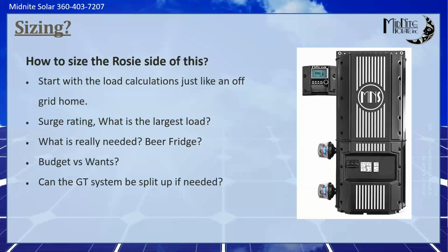But if the customer has, say, multiple strings of microinverters like Enphase or APsystems, then we can look at it and decide, hey, do we want to split those up, or do we want to put in 2 Rosies? Because let's say that same customer has 14 kilowatts of microinverters. Now what we can do is we can go up there and we can peel 1 or 2 strings out of the electrical panel, and feed them into the Rosie's backed up panel as AC coupled. And we have still met the 1-to-1 ratio. We've met all the customer's needs, and yet we've also kept their budget down on their backup, right? Some of the solar goes directly to the grid, some goes to the AC coupled.